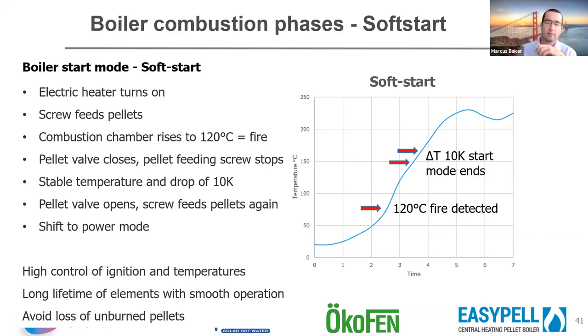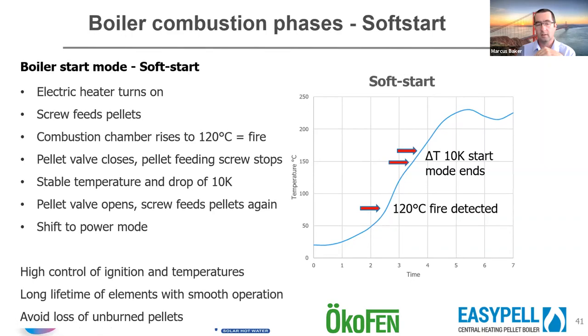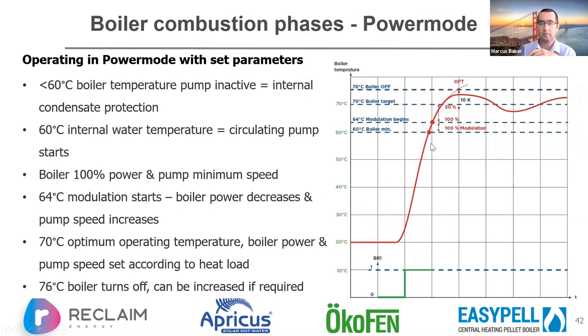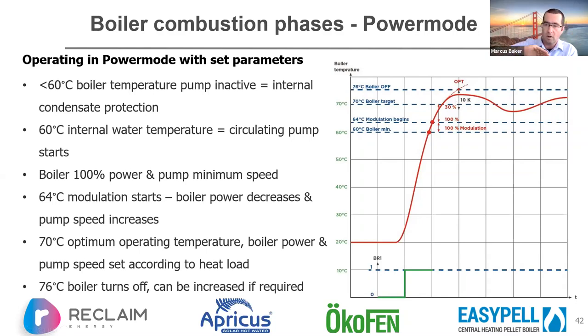Going from completely cold to starting takes a maximum of 15 minutes, usually much less. Hydraulic design considerations need to account for this, which will be covered in the next session. Once in power mode, the pump is released once the boiler jacket water temperature reaches 60 degrees, and modulation starts at 64 degrees — a very small difference — to avoid overshooting. The sweet spot is around 70 degrees; these can be modified but going higher reduces the window for a controlled shutdown.